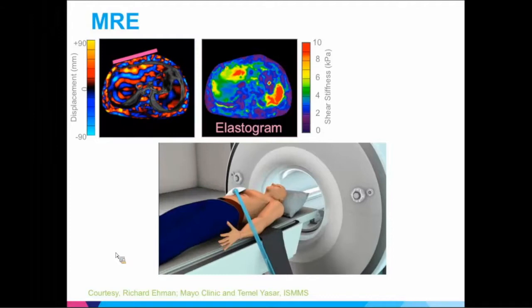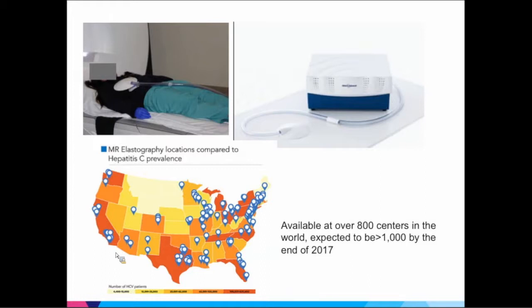The active driver produces the vibration and is put outside the MRI room because it's not MRI compatible — it's basically a speaker system. There were over a thousand of these systems in the world by the end of 2017, with many in the east, midwest, and California.